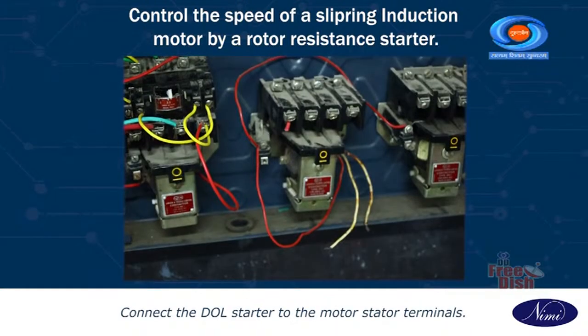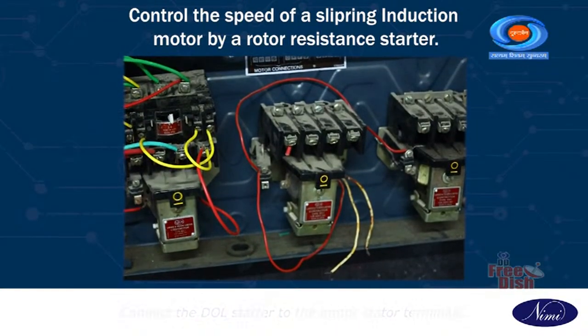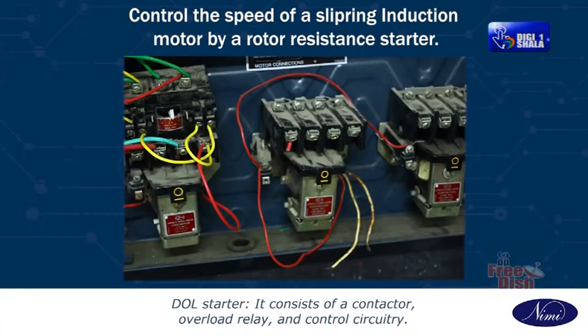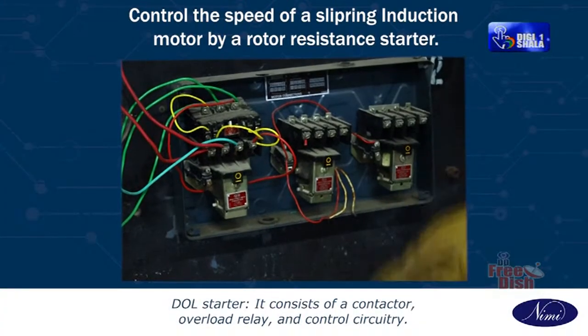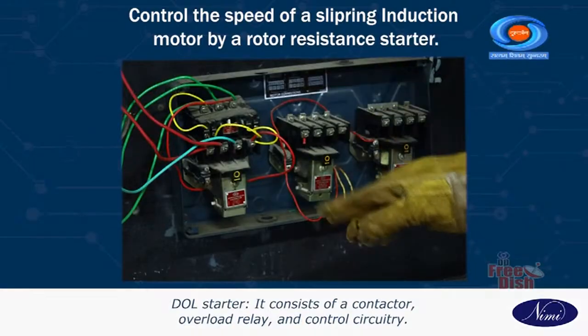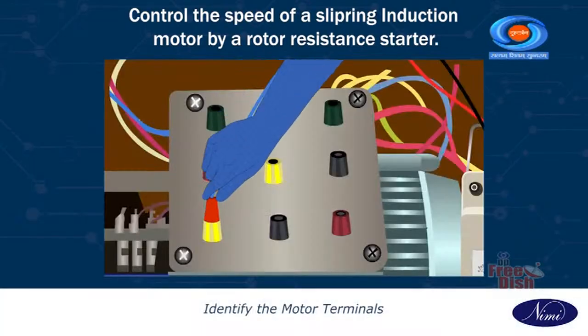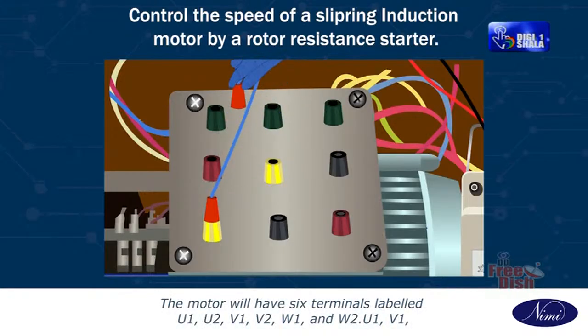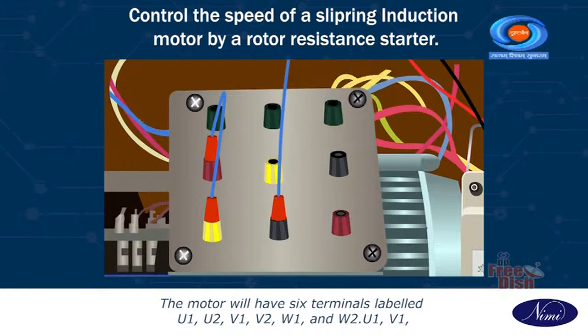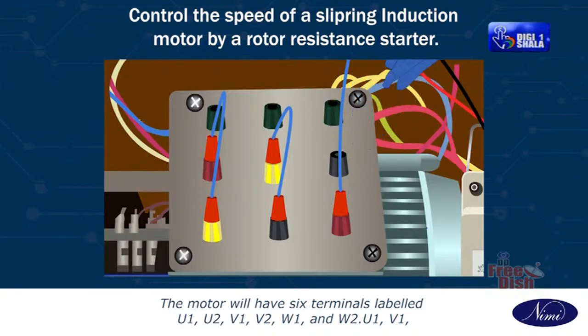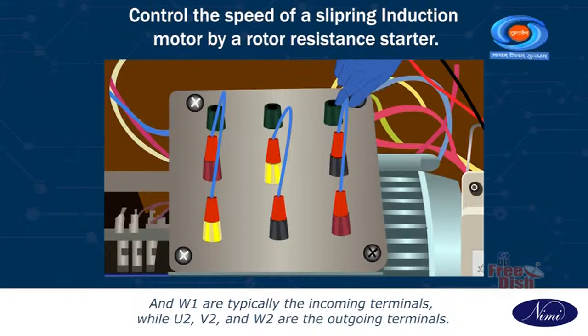Connect the DOL starter to the motor stator terminals. DOL starter. It consists of a contactor, overload relay, and control circuitry. Identify the motor terminals. The motor will have 6 terminals labeled U1, U2, V1, V2, W1 and W2. U1, V1 and W1 are typically the incoming terminals, while U2, V2 and W2 are the outgoing terminals.